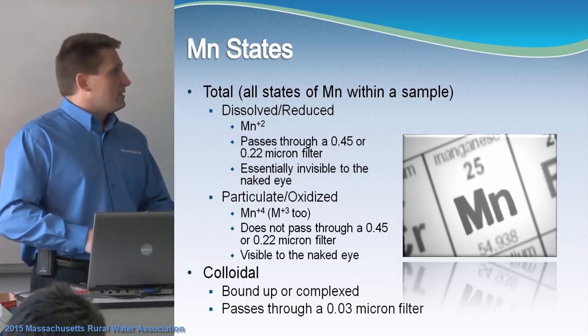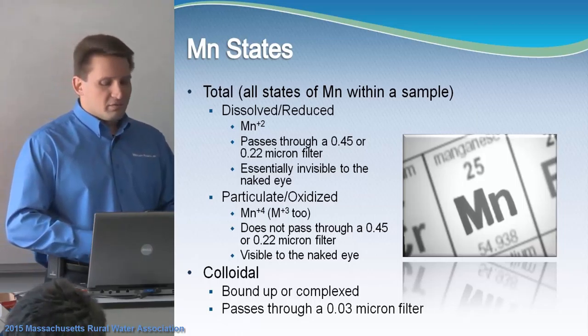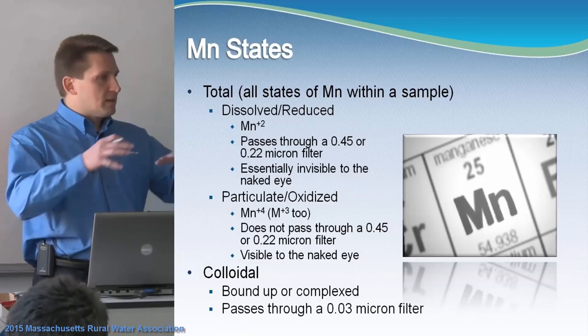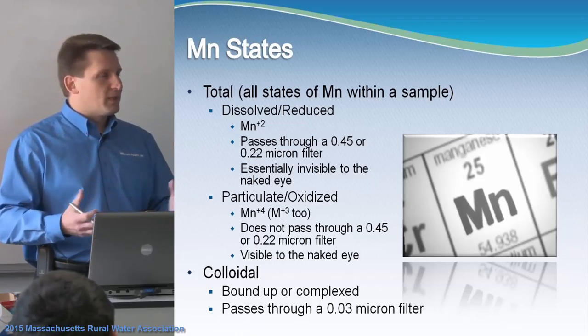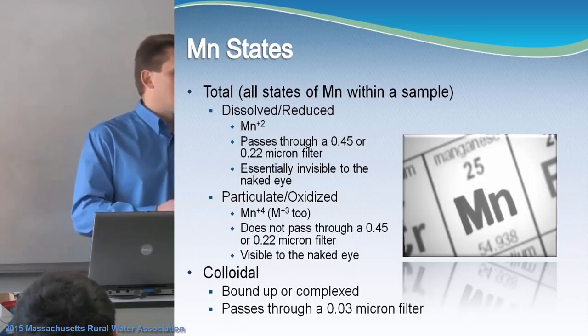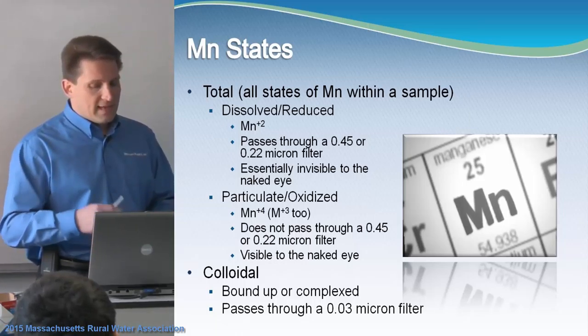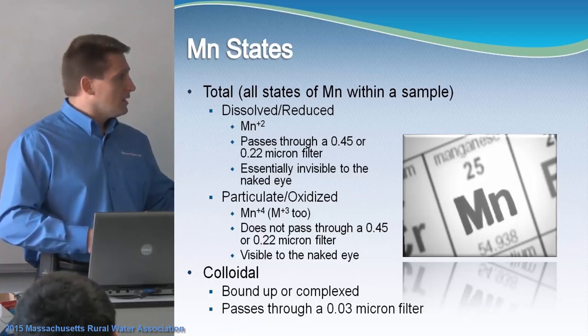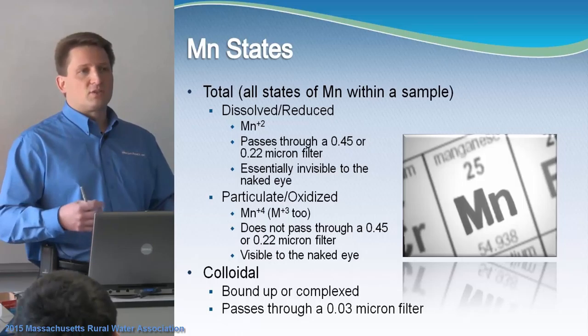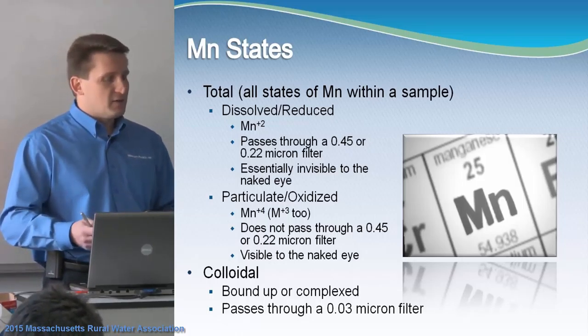Colloidal is another state of manganese that's important when it comes to treatment because it makes it very difficult to remove. Colloidal manganese is basically bound up or held in place by an organic — like natural colors in your water, leaves, humic substances. That makes it very difficult to remove. It can actually pass through a 0.03 micron filter, an even smaller filter, which tells you that at that state it's very hard to remove.